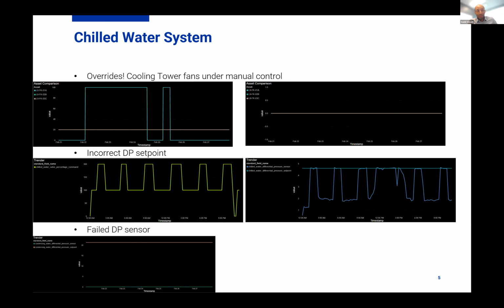The second one was the biggest concern I had: we had an incorrect differential pressure set point set up on our chilled water side. What actually ended up happening was that when the balancer was working with our controls contractor, they were communicating over phone or radio, and they took the reading, and they told them, all right, set this at 8 PSI. It's like, all right, perfect, we're going to put it in there. And they put it at a wrong location. So we had the pumps controlling to a significantly higher pressure.